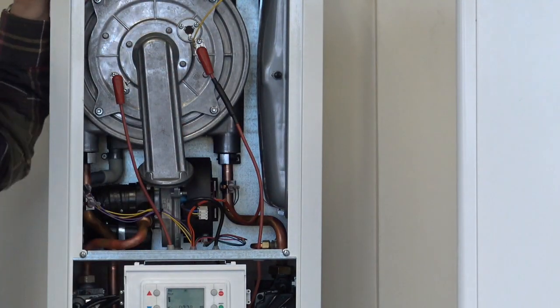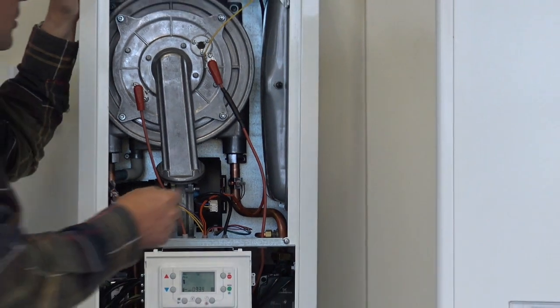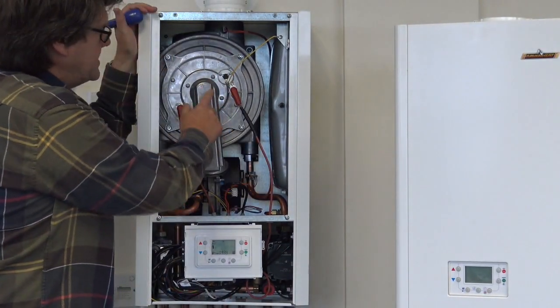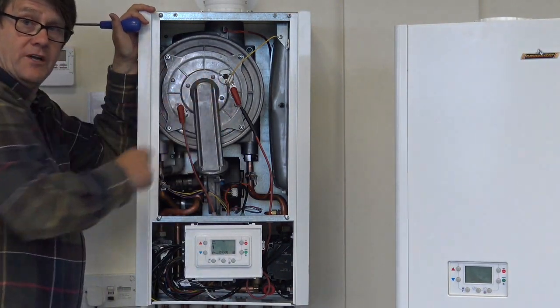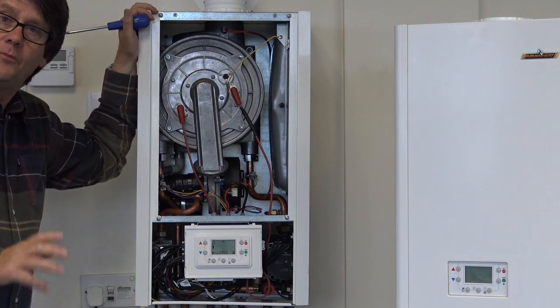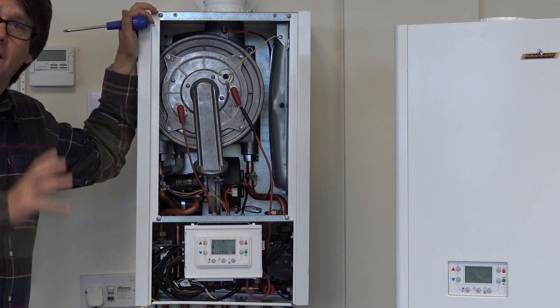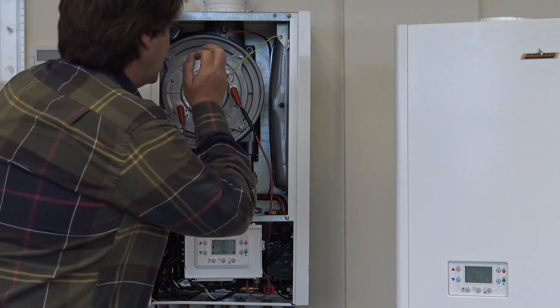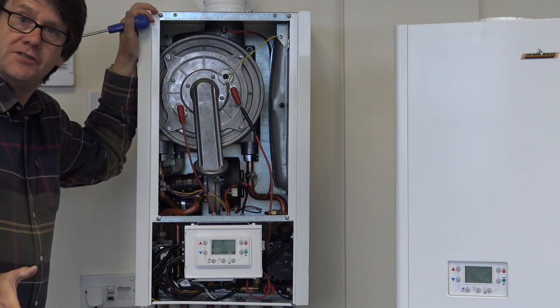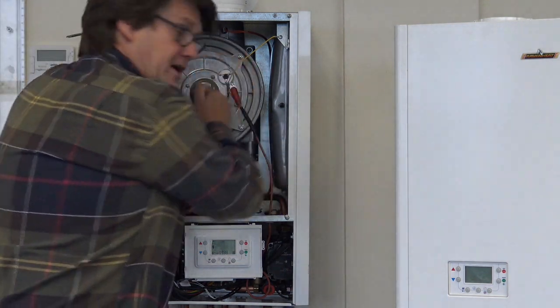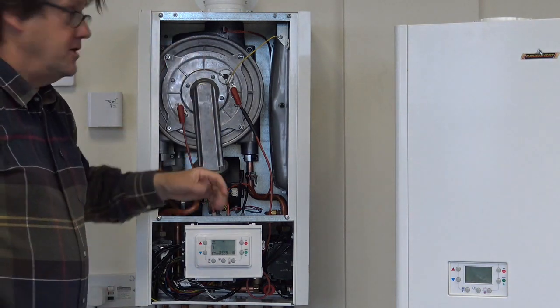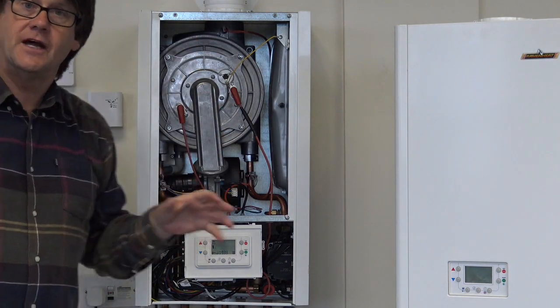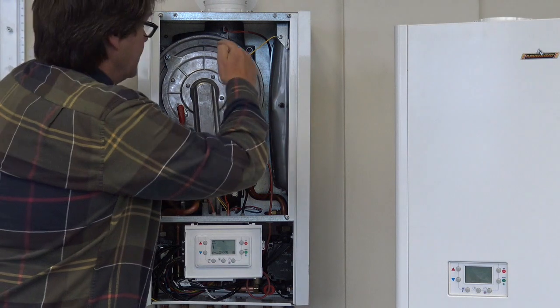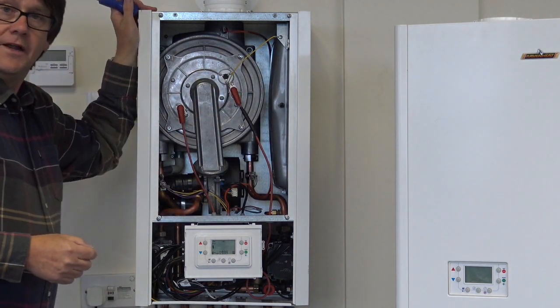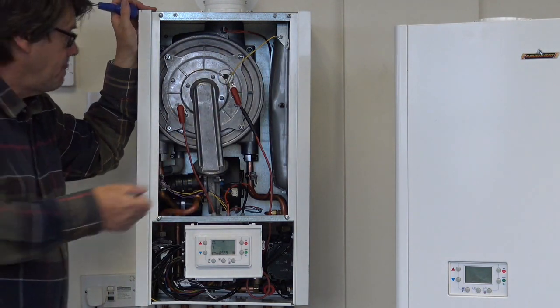Drop down. Let's look at the front of the heat exchanger. I'll address the heat exchanger shortly. But if you look on the front of the heat exchanger, we have a glass window. And that glass window in operation will not soot up, okay? It stays clear. And that is perfect for when you're doing annual servicing, because you can check the flame picture before you put your analyzer in. You know, it's like when you corrupt an analyzer, it's a nightmare. Well, with this, you can check that the flame picture is somewhere near before you stick that analyzer in.